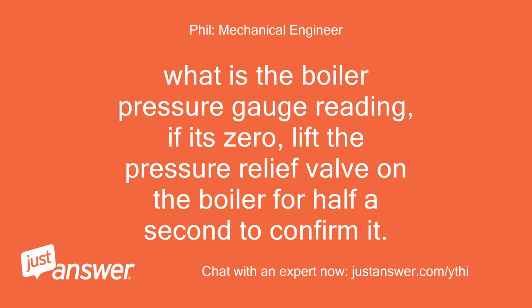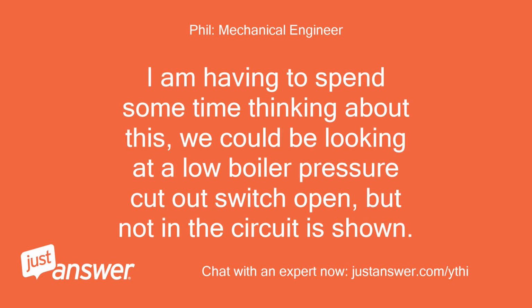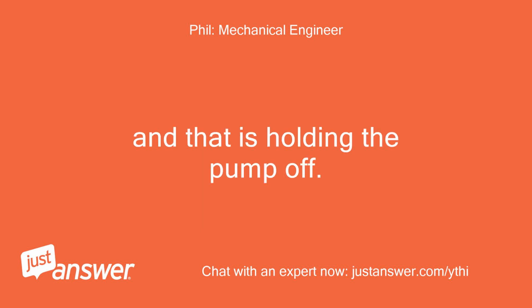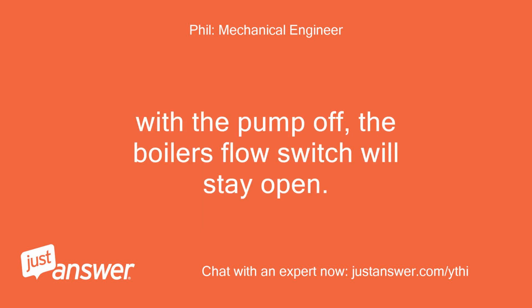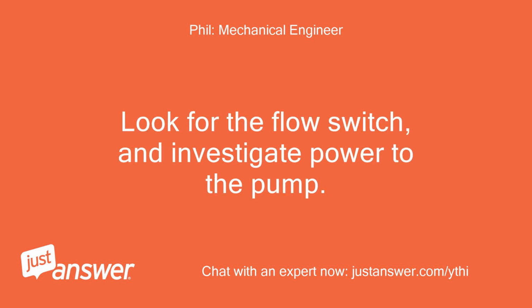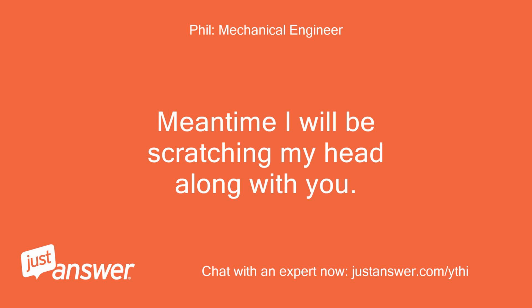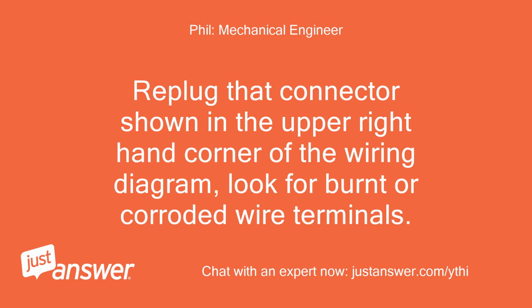What is the boiler pressure gauge reading? If it's 0, lift the pressure relief valve on the boiler for half a second to confirm it. I am having to spend some time thinking about this. We could be looking at a low boiler pressure cutout switch open, but not in the circuit as shown. And that is holding the pump off. With the pump off, the boiler's flow switch will stay open. Look for the flow switch and investigate power to the pump. Meantime, I will be scratching my head along with you. Replug that connector shown in the upper right-hand corner of the wiring diagram. Look for burnt or corroded wire terminals.